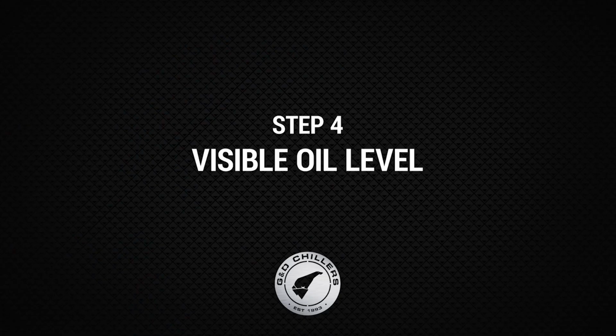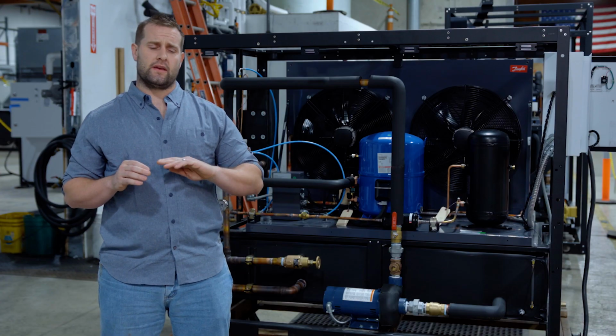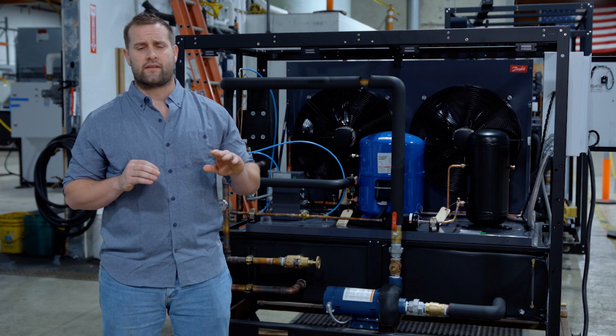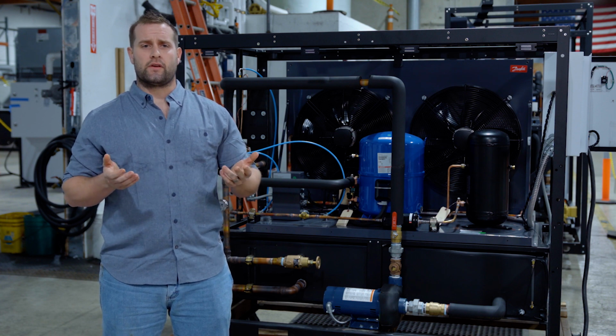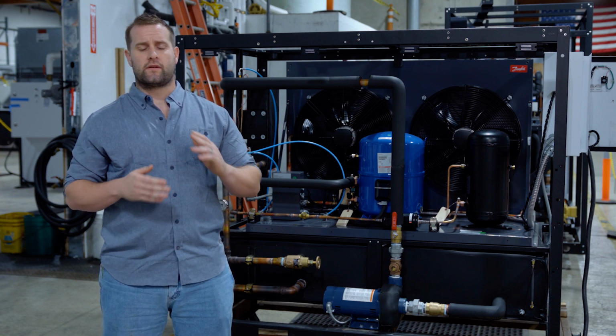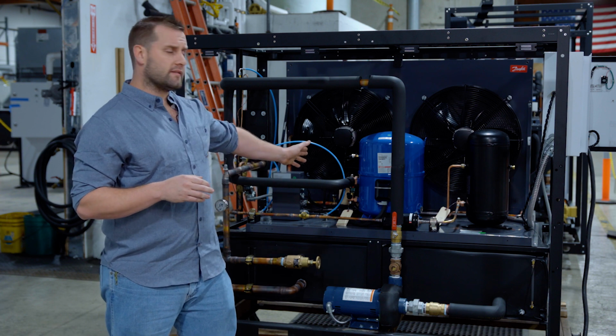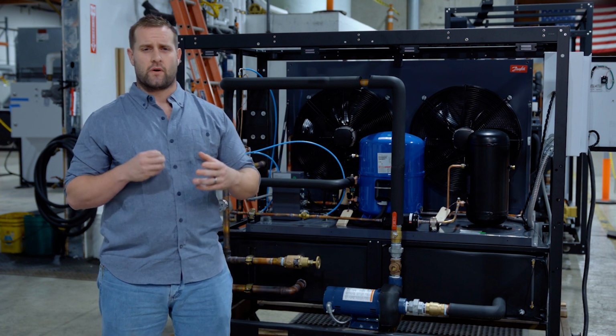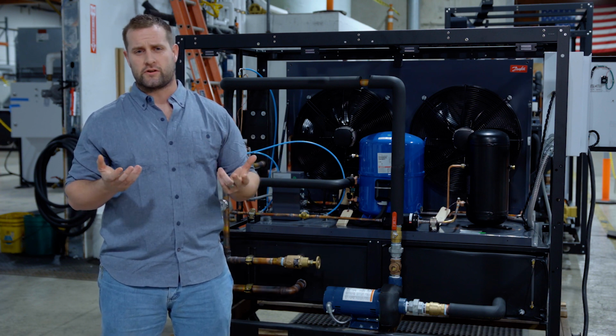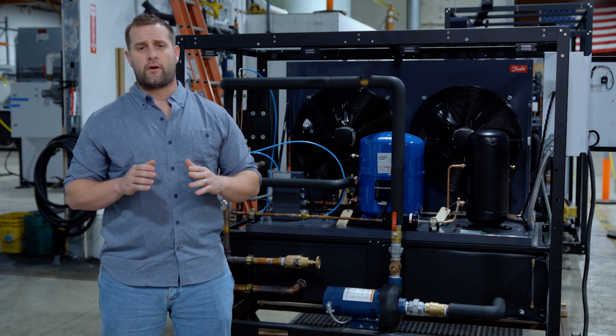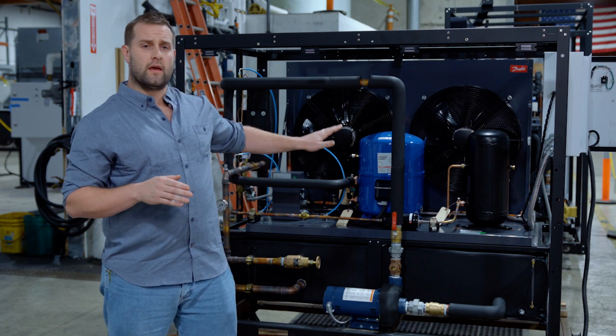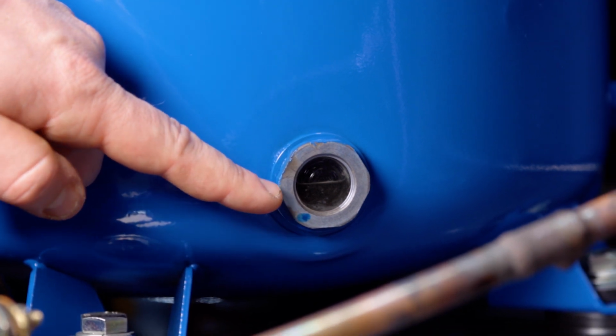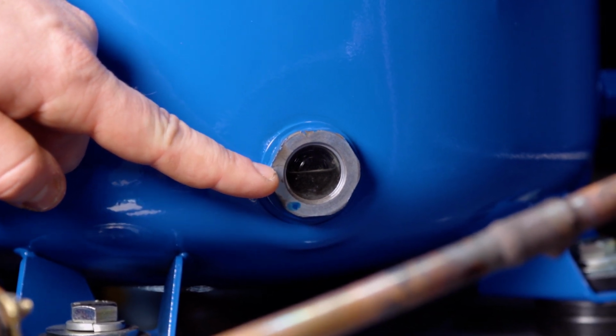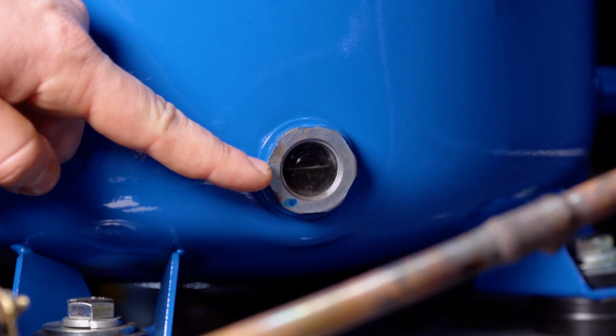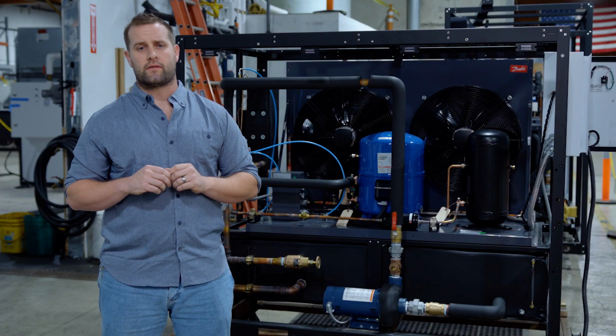The next step on the startup form is simply going to get your crankcase heaters energized. You'll see some verbiage on that step saying to keep the unit energized for 4 hours. There are crankcase heaters on the compressor, and what that's going to do is burn off liquid refrigerant. We want that on for a long period of time so you can see oil levels. If your compressors are flooded, you're not going to see that oil level. So when you're at this step, if you go to the compressor sight glass and you see a level in there, you're good to go to move on to the next step.